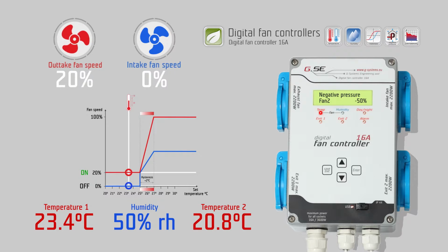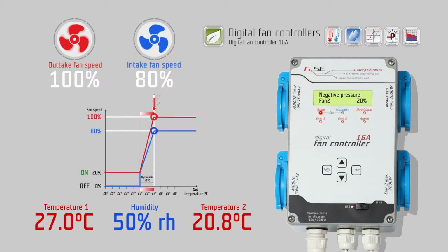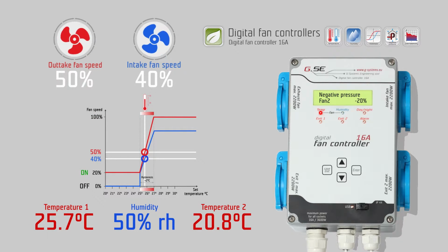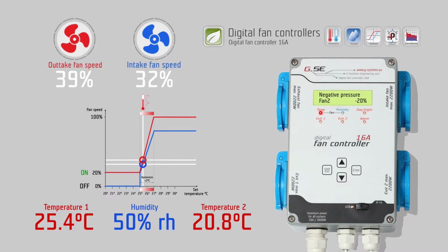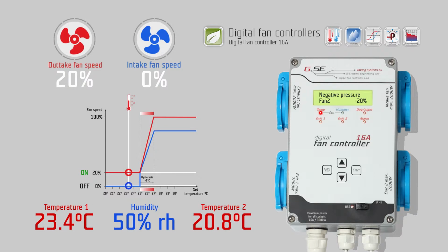Press down. The negative pressure reduces the fan speed of the intake fan. Both fans work synchronously. For example, we set the negative pressure to -20%. When the exhaust fan operates at full load 100%, the intake fan stays at 80%. If the exhaust fan runs at 50%, then the intake fan runs at 40%, -20% of its power. The exhaust fan removes more air from the room than the intake fan blows inside, and you obtain a guaranteed negative pressure during the regulation.